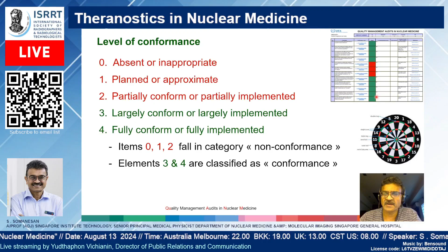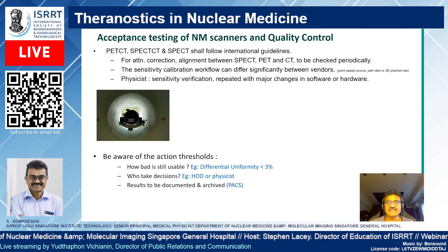Right. With that, let's jump straight into quality management in nuclear medicine, a synopsis and the practical aspects, especially slanted towards targeted radionuclide therapy. In essence, when you have theranostics, you need to do imaging. You need to do good imaging as well. So, of course, the equipment that you purchase needs to be properly accepted and properly commissioned by the medical physicists and engineers. For attenuation correction, for example, the alignment between the SPECT and the PET with the CT component needs to be checked periodically as well. The sensitivity and the calibration can differ significantly between vendors, and that needs to be checked as well.